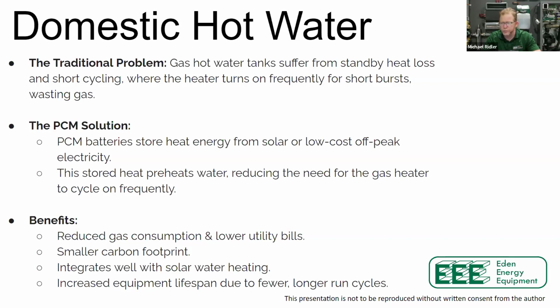We're going to store that energy, but because that PCM battery is storing sensible and latent energy, it's an even temperature. As we draw it down, it stays the same temperature. So if we charge that battery to 58 degrees C, roughly 140 degrees Fahrenheit, that's the temperature we're using until we draw that battery down. It's not like a stratified tank, which is quite unique.